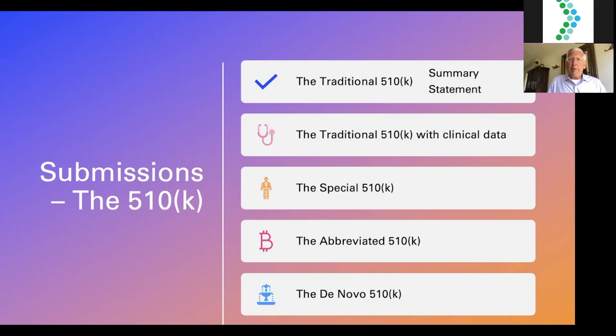Within the realm of the 510K, we have the traditional 510K, broken down into the summary traditional 510K or the statement traditional 510K. The most common is the summary traditional 510K, where you bring together all the information into a pre-market notification document that will serve as a ready reference as a predicate device for others in the future. The statement 510K puts across detailed information in a confidential manner and is less common, since most people prefer the summary format.